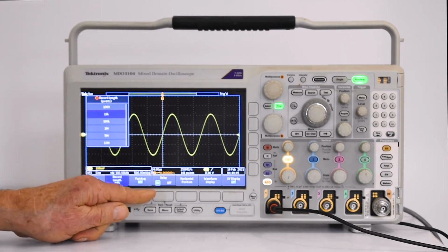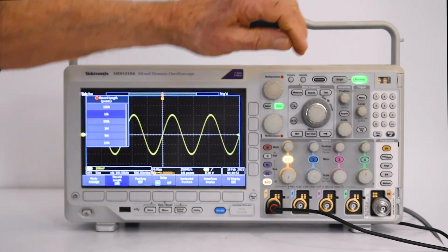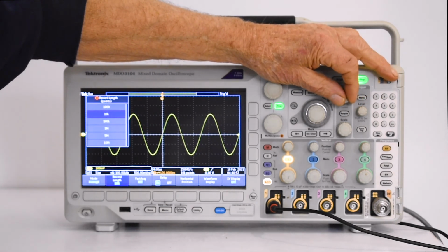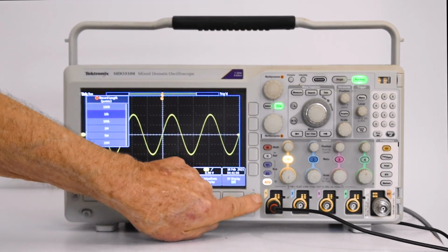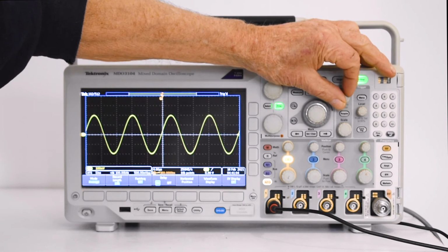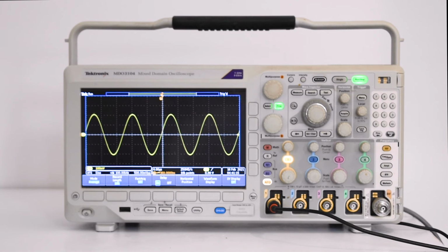With delay set on, turn the horizontal position knob counterclockwise to increase the delay. The trigger point will move to the left and ultimately outside of the original waveform. Then you can adjust the horizontal scale knob to acquire more detail around the area of interest at the center of the screen. When this delay is on, the trigger point separates from the horizontal expansion point.